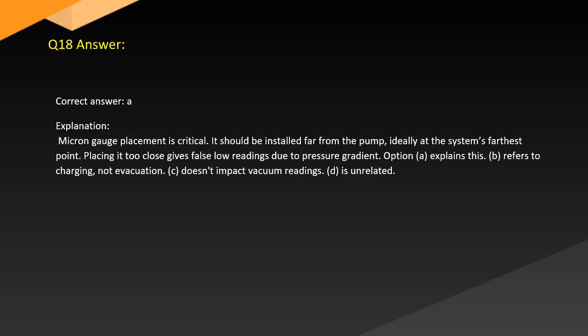Answer. Correct answer: A. Explanation. Micron gauge placement is critical. It should be installed far from the pump, ideally at the system's farthest point. Placing it too close gives false low readings due to pressure gradient. Option A explains this. B refers to charging, not evacuation. C doesn't impact vacuum readings. D is unrelated.